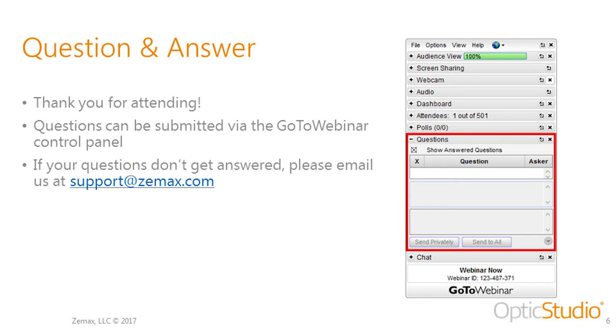The first question is: when you use the slider to adjust the parameters, is focus occurring also? I'm guessing this is referring to either the quick focus or paraxial focus adjustment. The answer is no — the slider and the visual optimizer are only changing the parameters that you see in the editors. There's no additional compensation or adjustment done once you manually change them or drag the sliders.